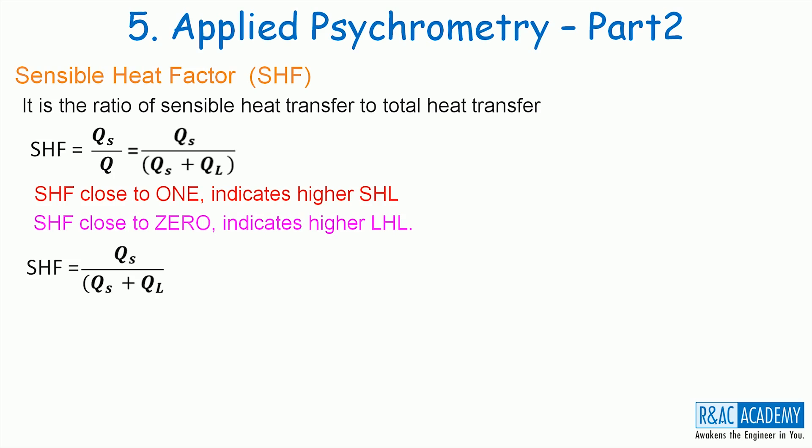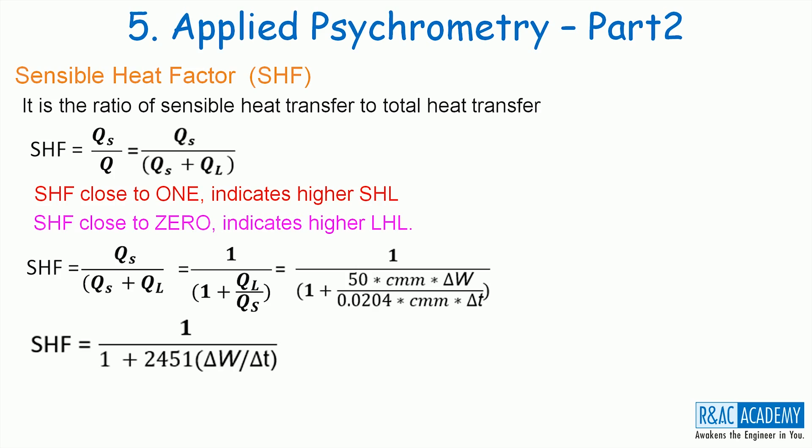The SHF expression can be rewritten by putting in the expressions related to QL and Qs. What do these terms delta W and delta T represent? Let us understand it using the psychrometric chart and consider process AC. If we draw a horizontal line from A and drop a vertical line from C, then they will intersect at B. During the process AC, the magnitude of change in temperature is represented by delta T and the magnitude of change in specific humidity is represented by delta W.